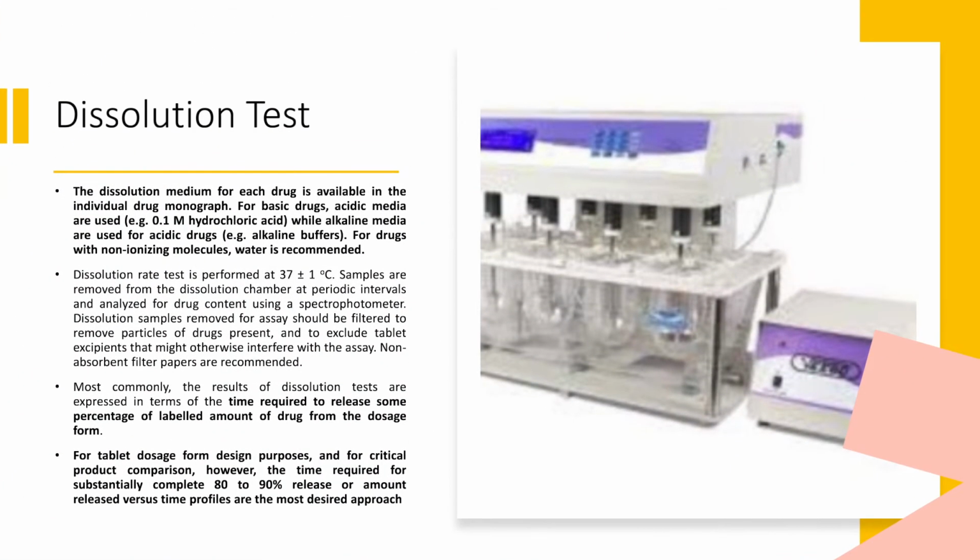So when we talk about the dissolution test, two or three things again are very important, as I have told in the disintegration test also. What are the temperature conditions to be maintained, what is the medium to be taken, and what kind of drug substance, and for how much time frame you have to do the sampling. So you can see this is the apparatus whereby you have basically six units, whereby you can add six tablets in each vessel at a time at frequent intervals of time as specified.